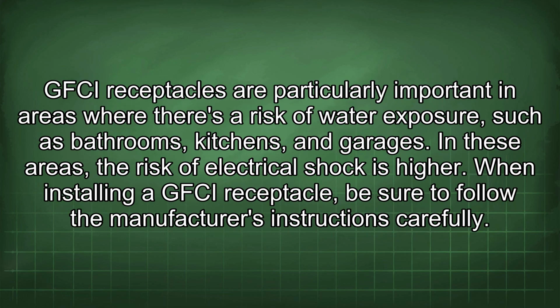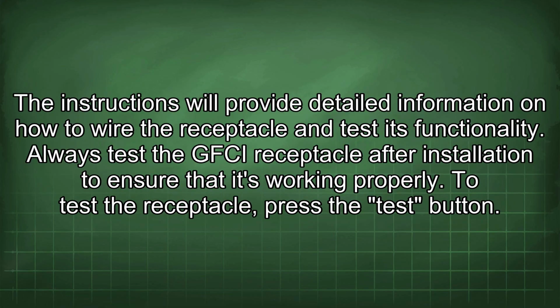GFCI receptacles are particularly important in areas where there's a risk of water exposure, such as bathrooms, kitchens, and garages. In these areas, the risk of electrical shock is higher. When installing a GFCI receptacle, be sure to follow the manufacturer's instructions carefully. The instructions will provide detailed information on how to wire the receptacle and test its functionality. Always test the GFCI receptacle after installation to ensure that it's working properly.